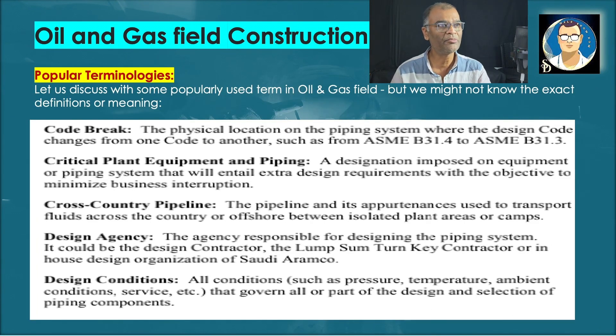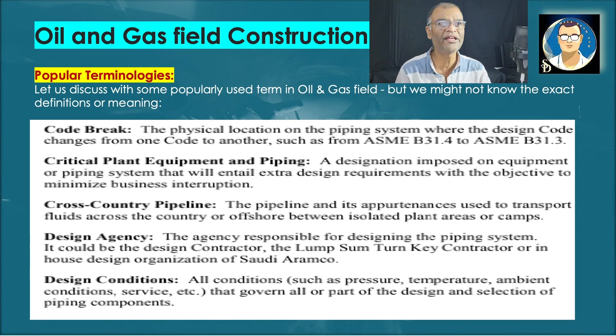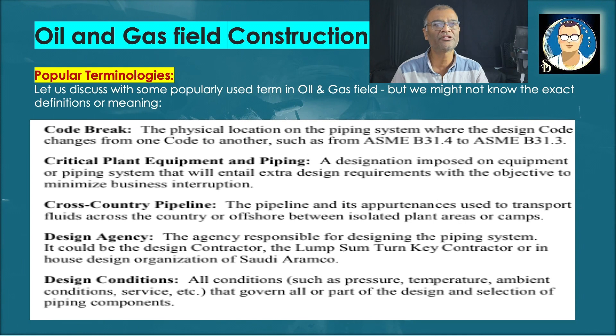Code break: let's say a pipeline coming from the desert or cross-country enters a plant area — there must be a code break. One code applies inside the plant for plant design, and another code applies for the pipeline up to that point. The physical location — specifically from which flange joint the code changes — is termed the code break. This term is used in ASME B31.4, B31.3, and B31.8.